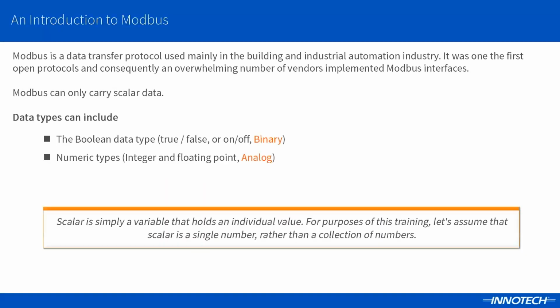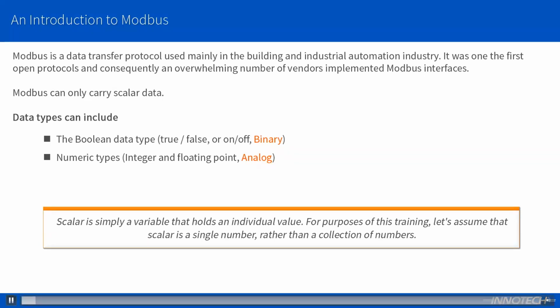In this video, we'll be covering the Modbus protocol and explain the functionality when applied to an Omni project in a simplified format. Many devices utilize the Modbus protocol, and they can be common devices installed on a typical BEMS project. The device data values that we are interested in from a Modbus device are usually binary and analog values that are stored as scalar data. This means that the format is a simple numeric value of various sizes in data length.